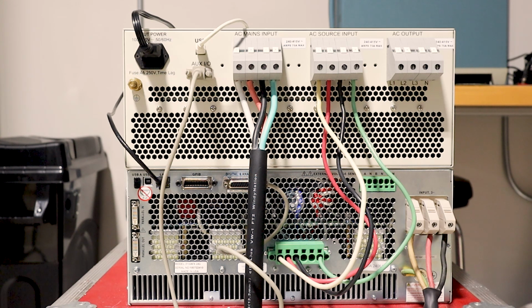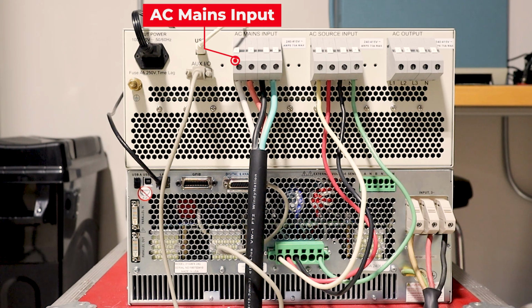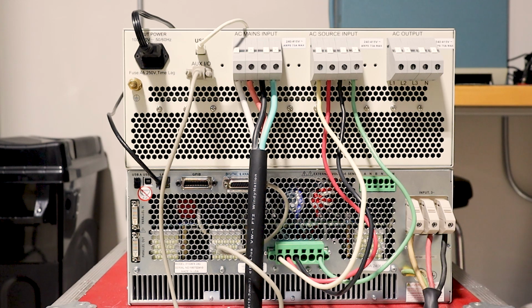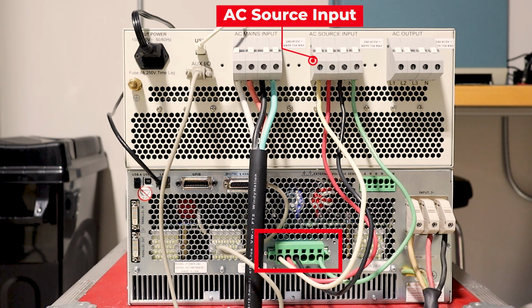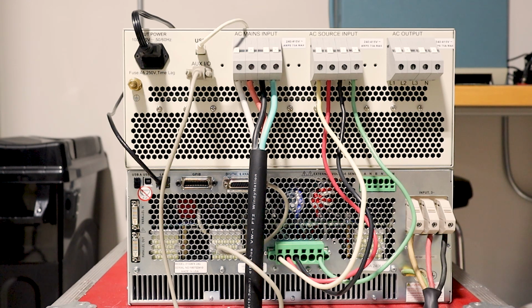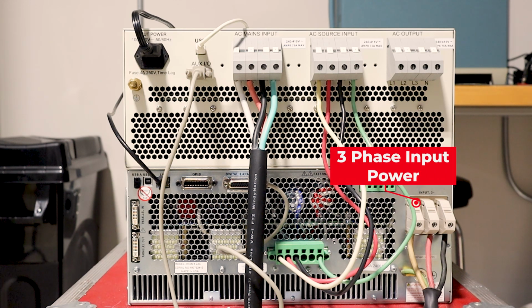Looking at the top section in the left corner on the back of the AFX, we have the LAN, which will also be going to the control computer. Taking a look now at the top section of our EPTS, working our way right, we have our AC mains input, which will be connected to the AC mains in our facility or our power supply. Next to that, we have the AC source input, which is connected to the green output on our AFX unit. To the right of that, we have our AC output, and that's going to our equipment under test. Finally, in the lower right-hand corner on our AFX unit, we have our three-phase input power.